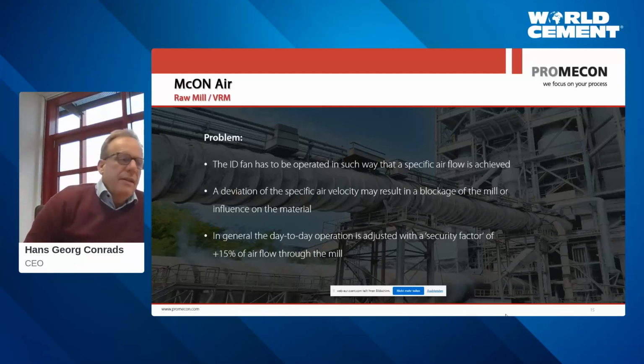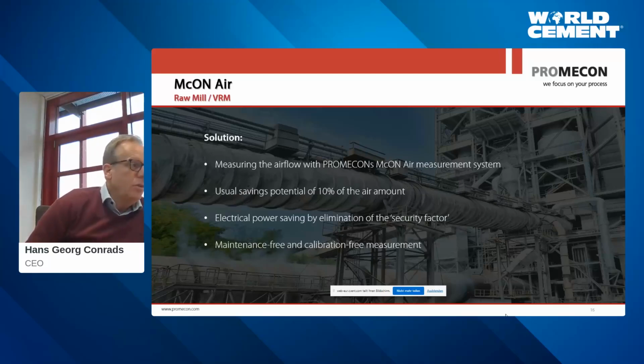Now, there are a couple of things here that give you a problem. One is, of course, electricity bill is one thing, electricity cost. The other thing is that you might also limit your ability to run the mill at full load. So also capacity factor comes into play. So the solution, of course, is fairly simple. The solution is that you measure the airflow accurately so that the operator can trust the airflow and can reduce the safety margin that he's overdrafting the mill with. And this security factor gives you back a lot of savings.